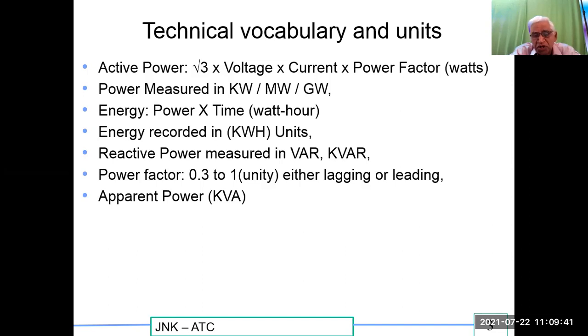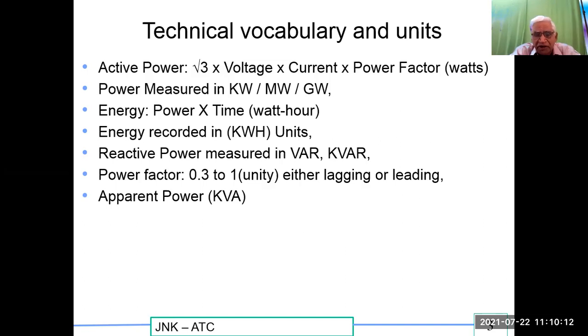Energy recorded is in kilowatt-hours, generally called units, and the units are mentioned in your electricity bill. Reactive power is measured in volt-amperes reactive (VAR), also in kVAR. Power factor is somewhere between 0.3 to unity, mostly lagging. When you connect power factor improvement capacitors it goes leading, but our aim is always to retain it around 0.95, plus or minus. Apparent power is measured in kVA, and transformers are always rated in apparent power.